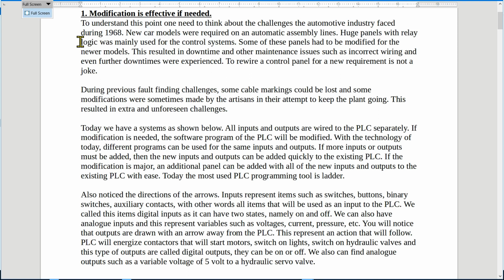To rewire a control panel for a new requirement is not a joke. I think we all went through this process where we design a panel and we think it's perfect. Just by the next day or the next week, a new request will be made and say, we now need to add a conveyor to this machine. And then this complicated the whole matter. And while we're doing this modification and adding on to this panel, we will find out that during previous fault finding challenges, some cable markings could have been lost and some modifications were sometimes made by artisans in the attempt to keep the plant going.